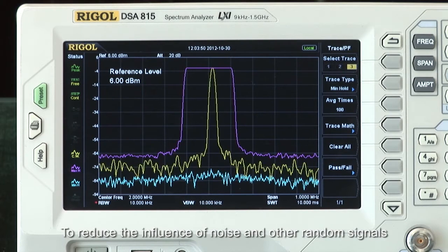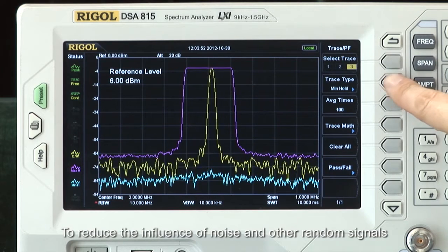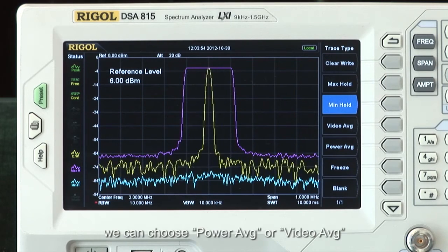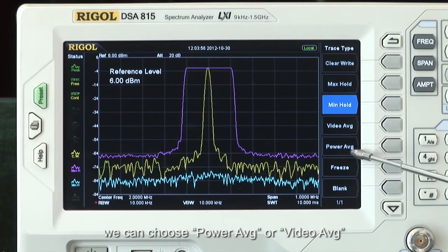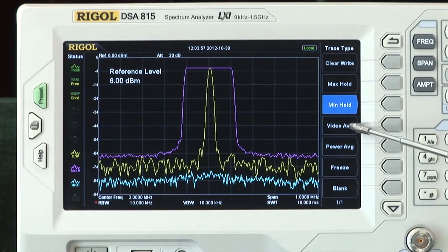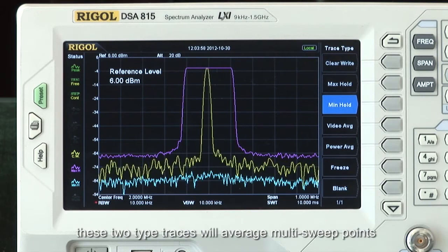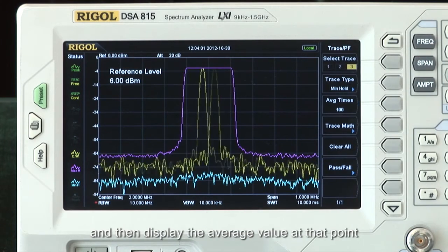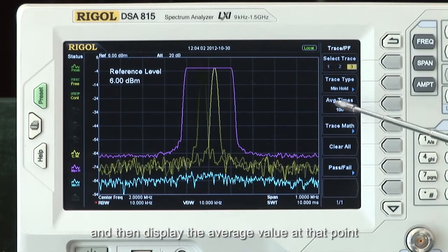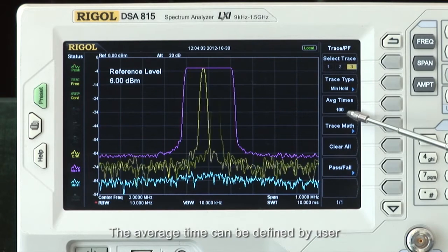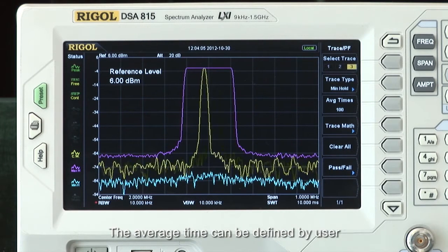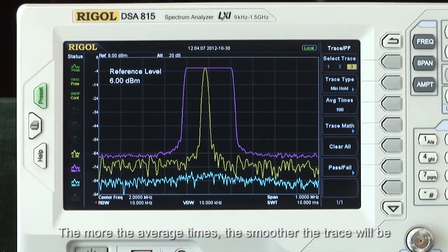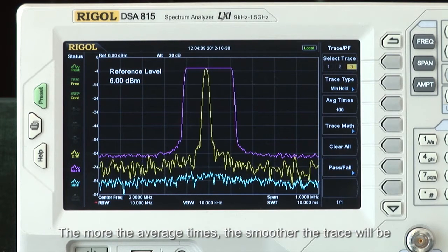To reduce the influence of noise and other random signals, we can choose Power Average or Video Average. These two trace types will average multi-sweep points and then display the averaged value at that point. The average count can be defined by the user — the more average times, the smoother the trace will be.